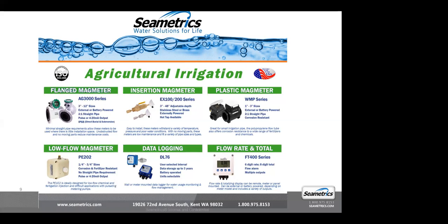We have an insertion mag meter. Those are very popular too if you don't need as high of an accuracy. They're very economical. And then for smaller line sizes, when you're looking at drip or really small line sizes, there's a 1 through 3 inch meter. These are just some examples of them. The ones you're looking at up here are all mag meters.